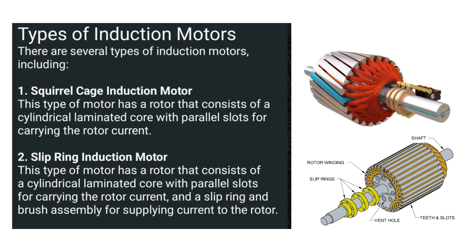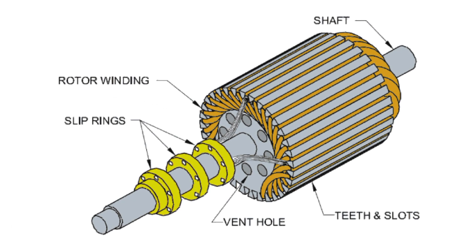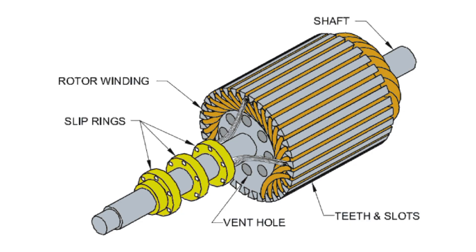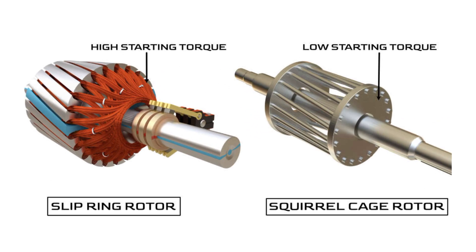The second type is the slip ring induction motor, which is also very important. We use this type of motor where high starting torque is required. These motors consist of a cylindrical laminated core with parallel slots for carrying the rotor current, along with slip rings and brushes for supplying current to the rotor.